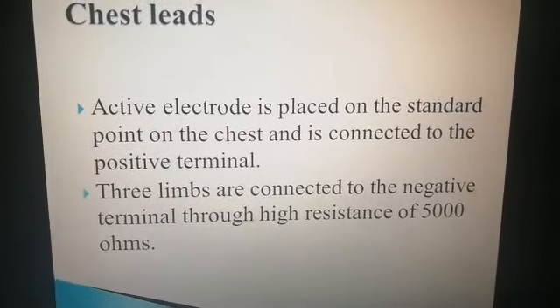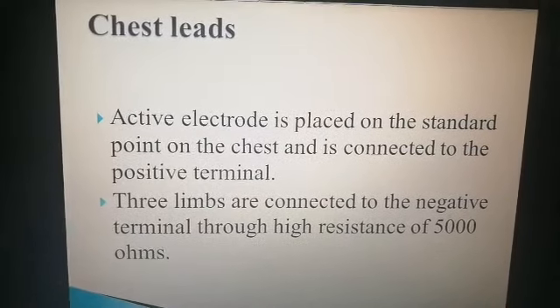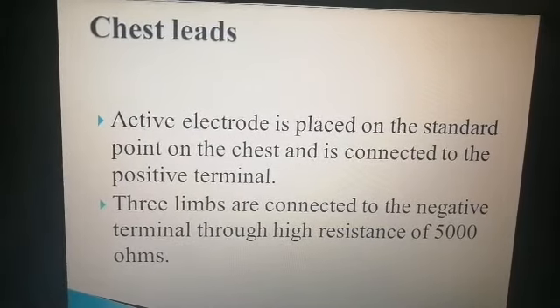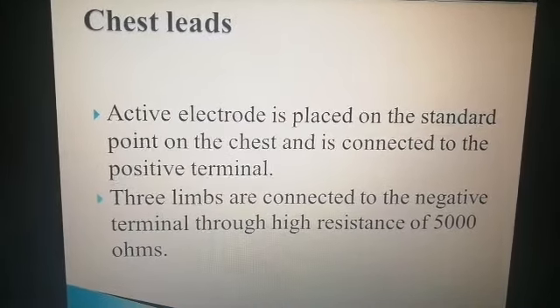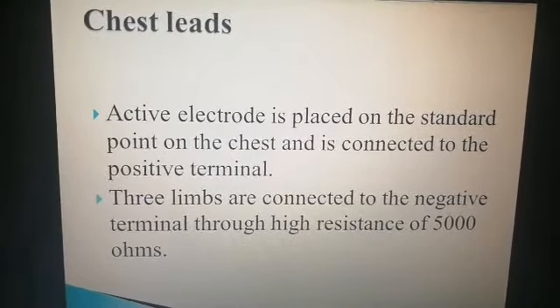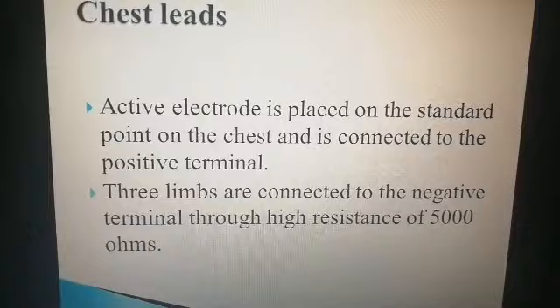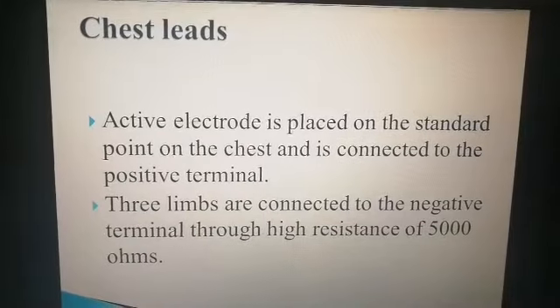The second type of unipolar leads is precordial chest leads. The active electrode is placed on a standard point on the chest and connected to the positive terminal. The three limbs — left arm, right arm, and left foot — are connected to the negative terminal through high resistance of 5000 ohms. The right foot is not included because it is neutral.